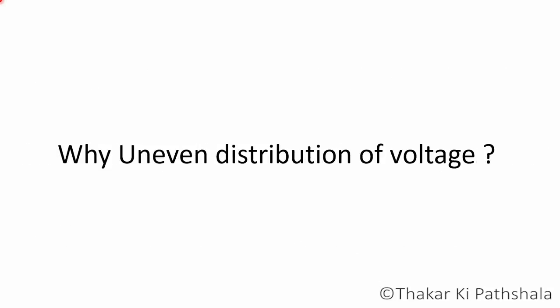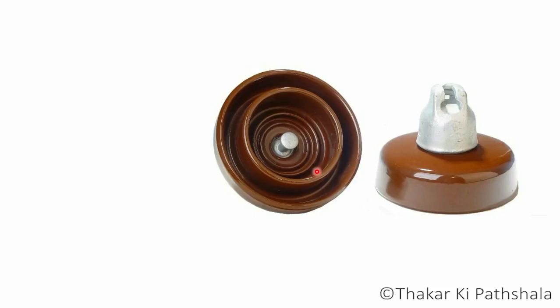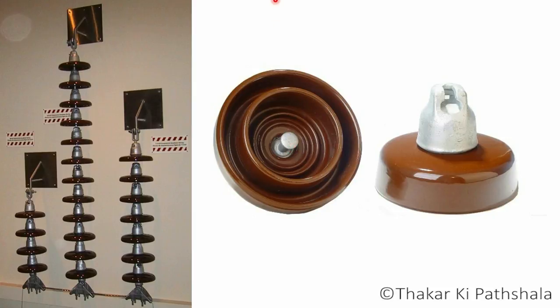First of all, the root cause of all this is uneven distribution of voltage. If you look at a high voltage transmission line, you will see a string of disc type insulators, and if you notice, the insulator disc has metal fittings on it. These metal fittings are conducting and the porcelain disc is the insulator. So a certain amount of capacitance is being formed between the metal fittings.